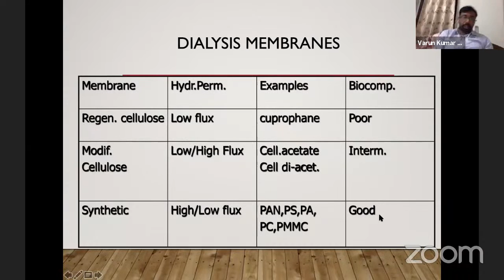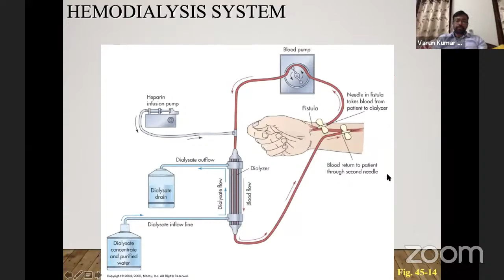This is how it goes. Fistula: always blood is taken away from the heart and blood is pushed towards the heart. So you take blood from the vein, the pump pulls the blood out, and it is pumped through a dialyzer. To prevent clotting inside the circuit, heparin is given. Once in the dialyzer, again you have the counter current flow of dialysate, blood flowing this way, dialysate flowing this way, diffusion happens, and the waste dialysate is thrown off. The filtered blood is sent back to the body. So this is a very complicated image. This is the blood pump. This is the dialyzer here. This is the acid and bicarb cans, and the waste dialysate goes at the back.